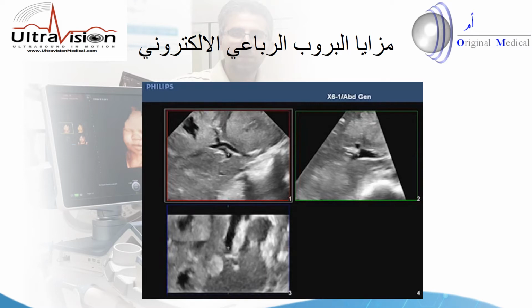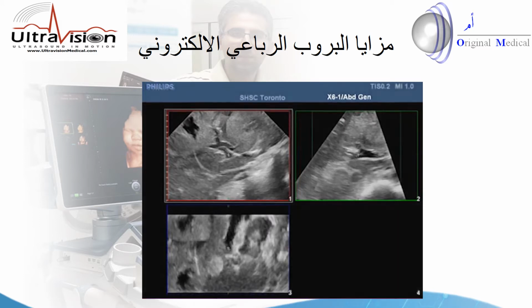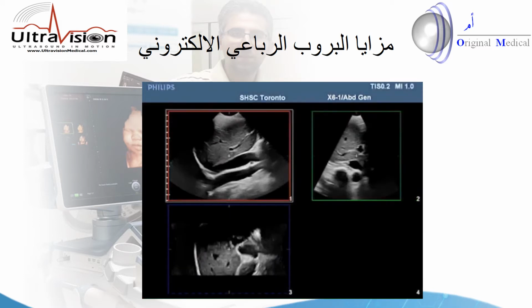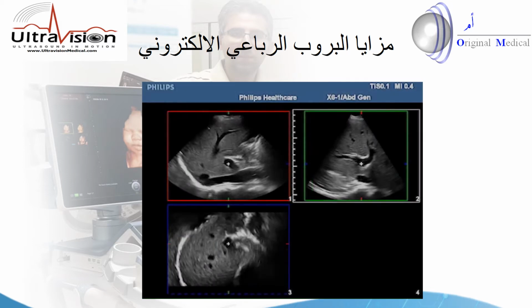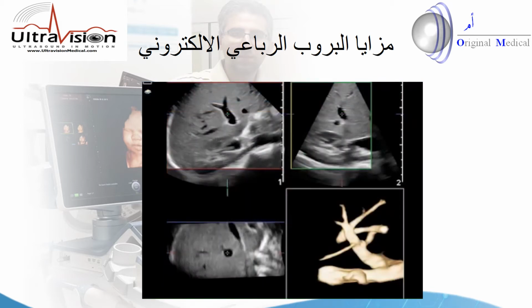And this enables us not just to produce two orthogonal planes, but to reconstruct, in fact, a plane that we never see with conventional ultrasound imaging, the C-plane, the plane that's at constant depth from the transducer, the one that's orthogonal to the two right-angle B-mode planes we can obtain by rotating a conventional transducer, or live using the X6-1 in X-plane mode. And here you can see the two X-planes with the C-plane below it.